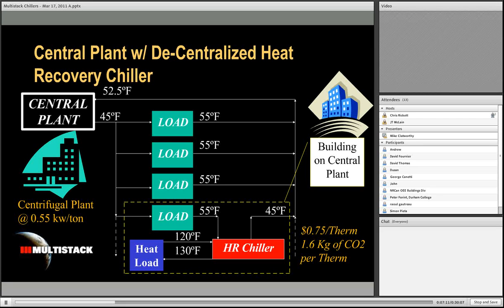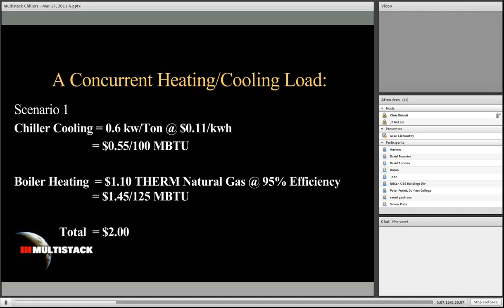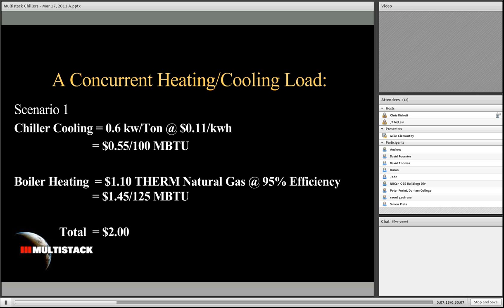You can see that the heat recovery chiller has been integrated. We're taking heat from the chilled water loop. We're causing the central plant not to work quite as hard, and we're taking that heat and passing it off to the heat load. But specifically, I want to show three different scenarios of a concurrent heating and cooling load. The first scenario would be a typical chiller-boiler application, where we have a chiller and a boiler. They're not helping one another.